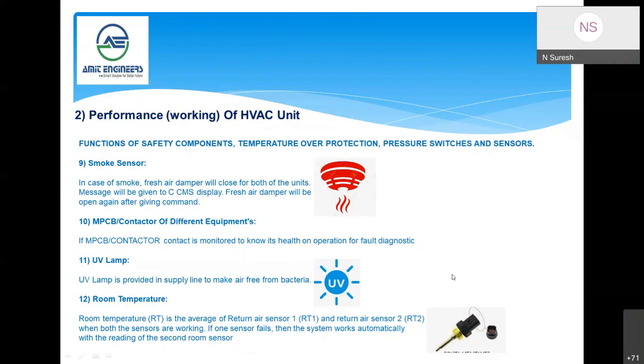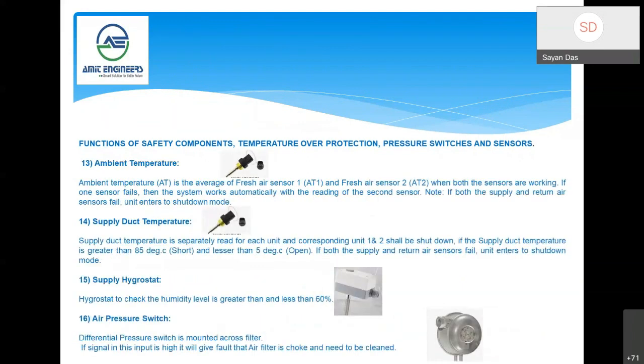And whenever the blower is running, this UV lamp will work. When the blower is not working, the UV lamp will switch off. That is how the logic is designed. So even in case of maintenance, whenever the blower is running, it will work, and before opening the door the blower will be off, and we can do the needed maintenance. These are all the temperature sensors. One is the room temperature sensor and the return air temperature sensor, and there are also the fresh air and supply air temperature sensors.